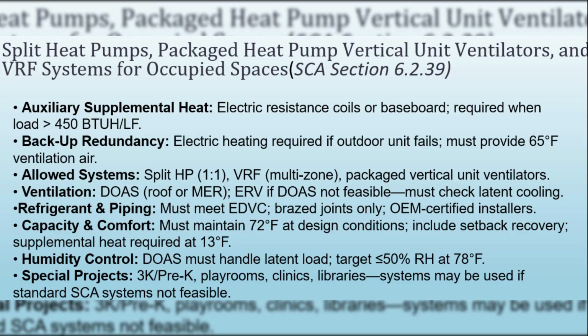Heating capacity must be calculated without relying on passive heat sources like lighting or occupants. Units must be capable of maintaining 72 degrees Fahrenheit during winter design conditions and reheating setback spaces from 55 degrees Fahrenheit. Because heat pump performance drops at low temperatures, supplemental electric heat is always required at 13 degrees Fahrenheit design conditions. Finally, designers must also account for humidity control. Since split and VRF terminal units have limited dehumidification, the DOAS units should be designed to handle latent loads, keeping spaces below 50% RH at 78 degrees Fahrenheit. In special cases, like pre-K classrooms, playrooms, libraries, or clinics, these systems may be used more widely, provided they meet SCA requirements and project-specific constraints.